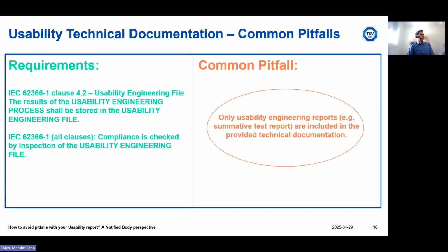Clause 4.2 actually is quite straightforward. The results of the usability engineering process shall be stored in the usability engineering file. And in all the clauses of the standard, it is written that compliance with the requirements of the standard is checked by inspection of the usability engineering file. So the usability engineering file shall be present in the MDR technical documentation, but a common pitfall is that it is not always present. Sometimes only summative test reports or formative test reports are provided or available.